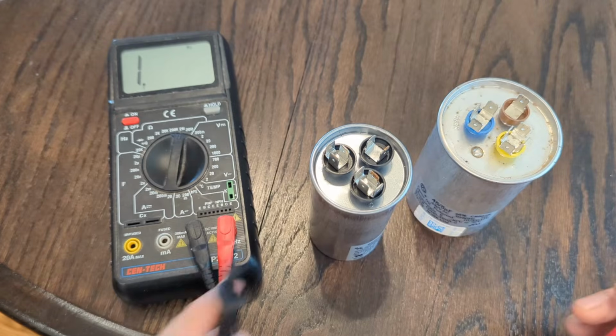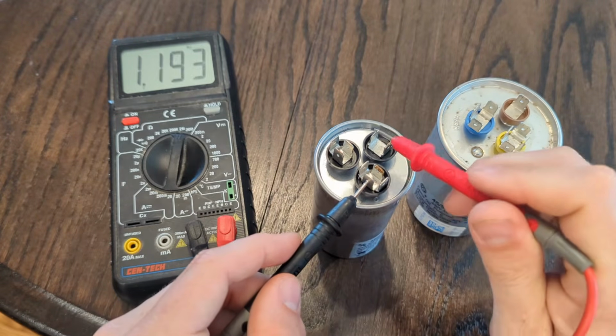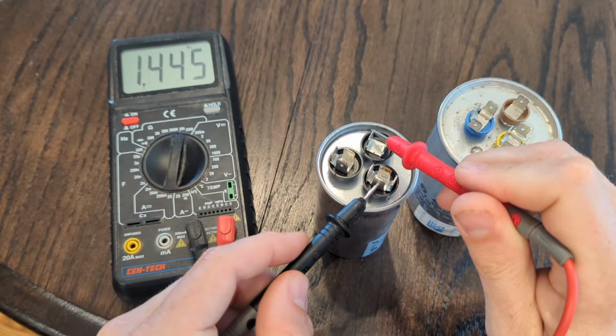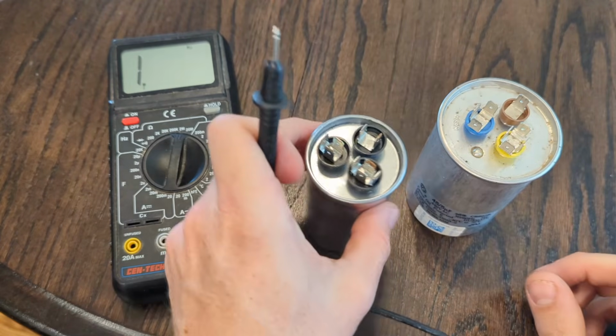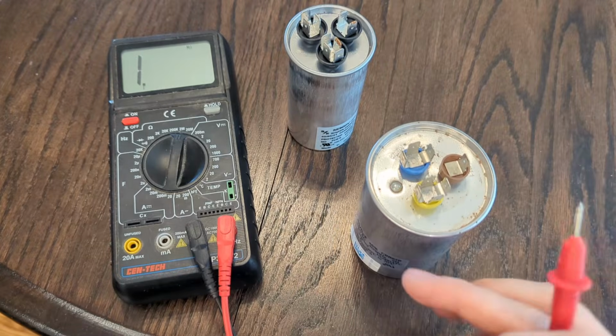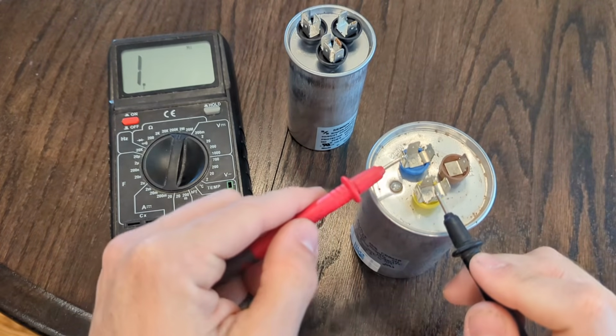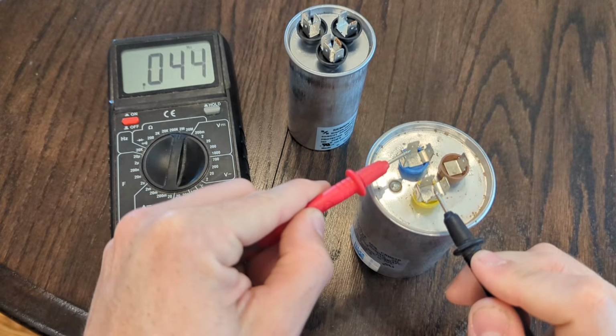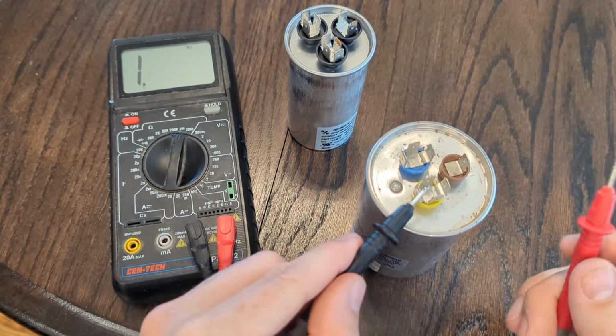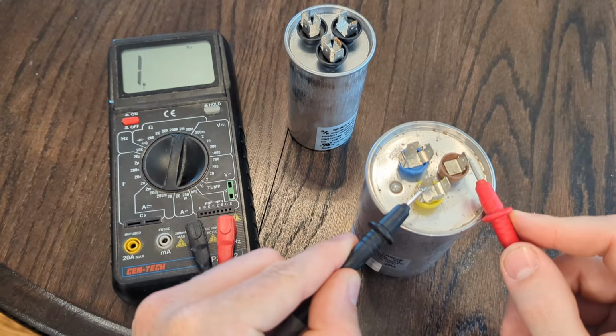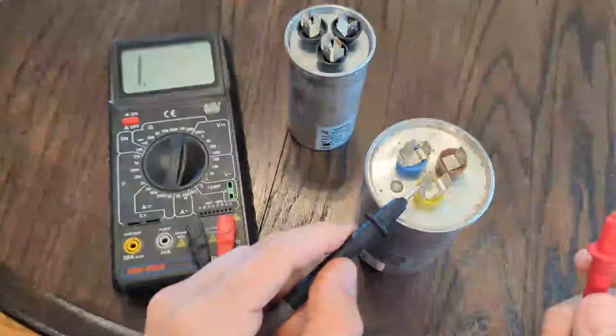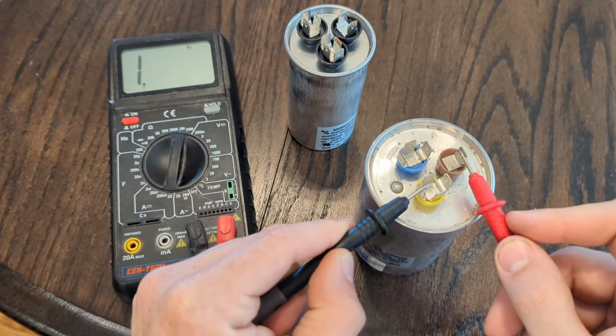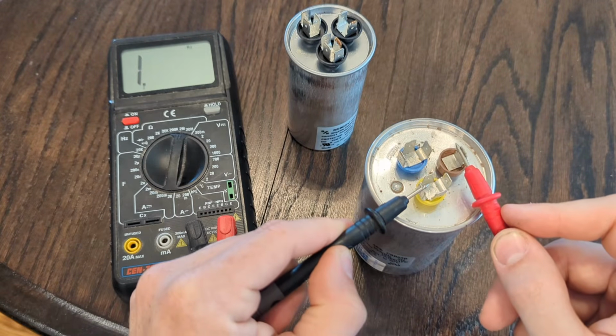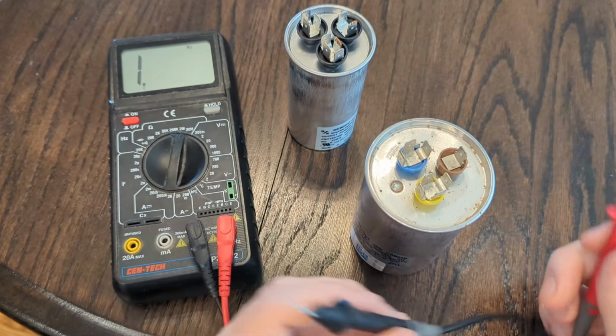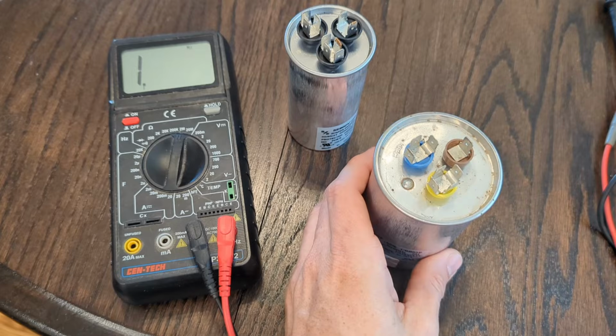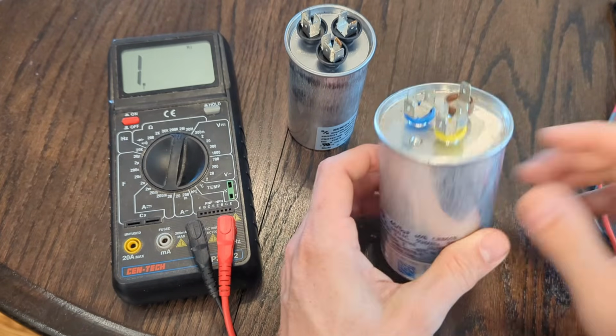Okay, then we're going to go to the other side. Black to common, red to fan. You see it jump. Okay, set that one aside. Now let's see the difference. If we go black to common, red to Herm, there's a jump. Black to common, red to fan, nothing happens. Do it again. Black to common, red to fan, no reaction. This means there's nothing going on between these two. Capacitor has failed.